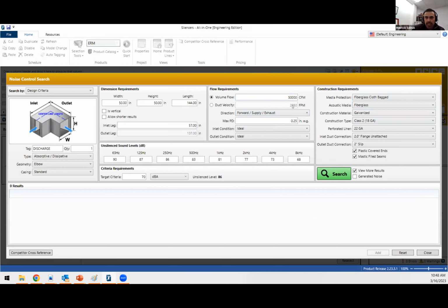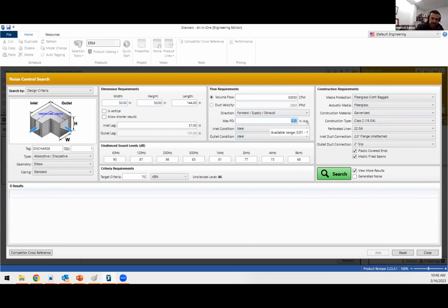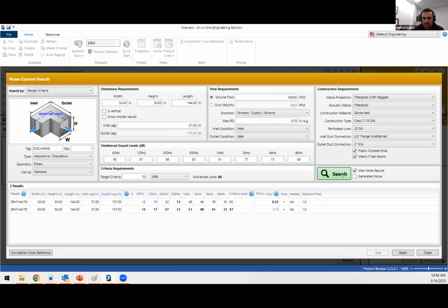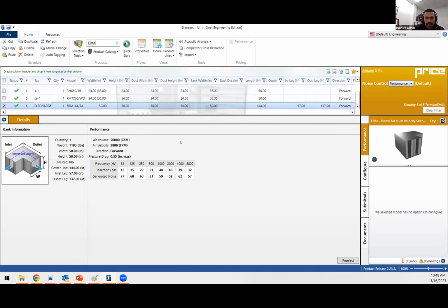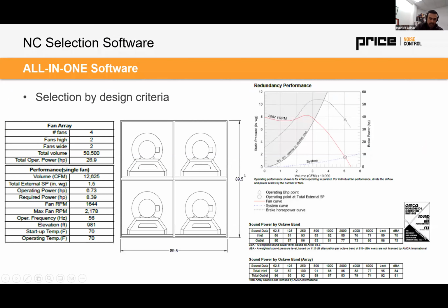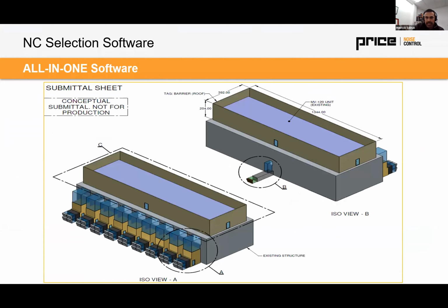Now, this is face velocity based on 50 by 50, right? But when you are putting air through a silencer, you are constricting the air by at least 50%. So the speed going inside the silencer is going to be much higher than that. That's why you're trying to add a fiberglass cloth bag in it. Now, if you want to keep it at 60 dBA at 0.5 inches of pressure drop, then that's what you would be adding for that specific scenario. So in this specific scenario, they were doing 9 arrays into a generator room, and then they were sucking all the air through the top. And it was 9 inline generators.